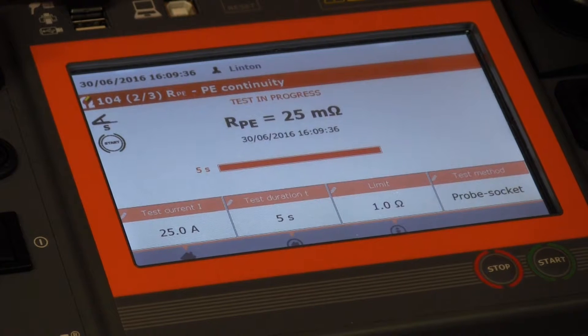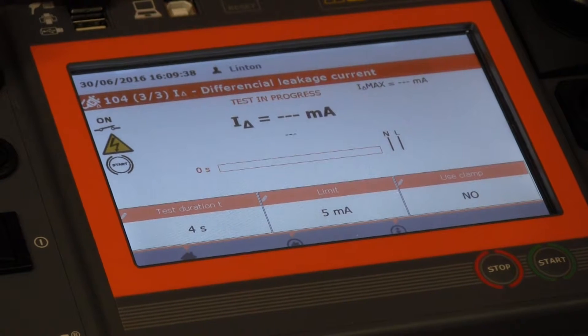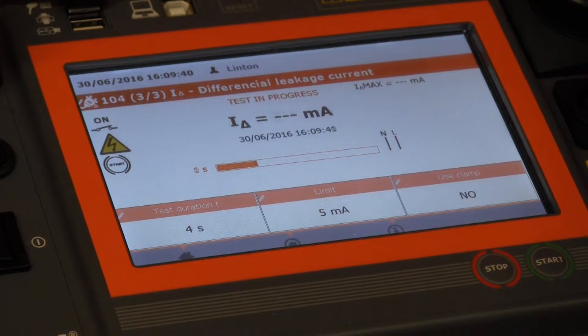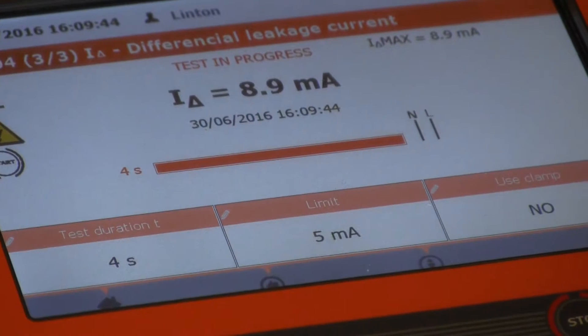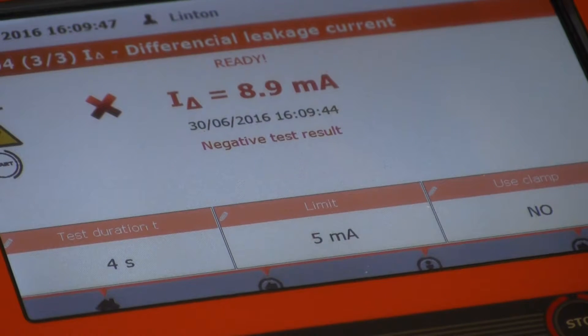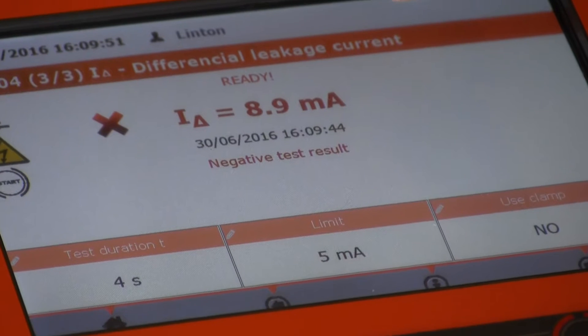It's just about 25 milliohms and now it's going to put the switch on and it's now doing a powered-up leakage test. If we look at the leakage it's 8.9 milliamps and you can see the screen's gone red, which tells me that it's a fail.